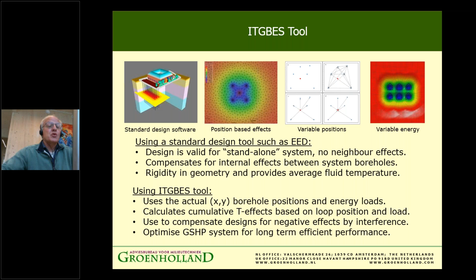You can use it to compensate your designs for the negative effects of interference from other systems. You calculate what the effect is, then compensate your design in accordance with whatever you've agreed with your client or designer, and optimize the ground source heat pump system for long-term efficient performance, because losing temperature due to neighboring systems reduces your performance in the long term.